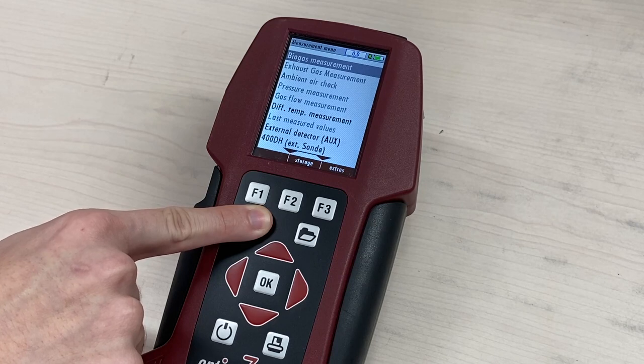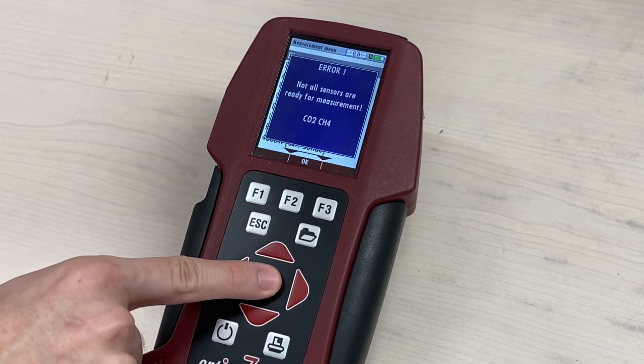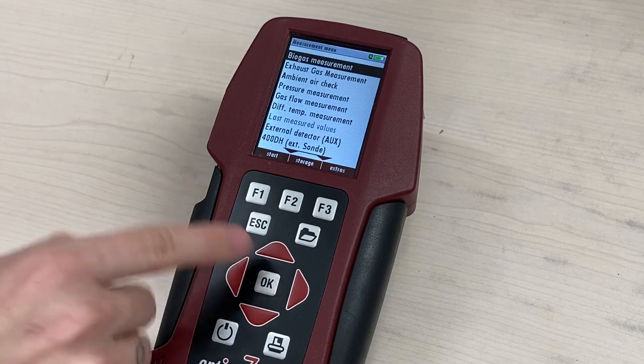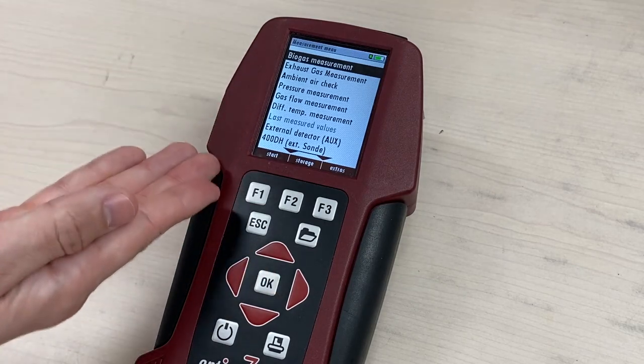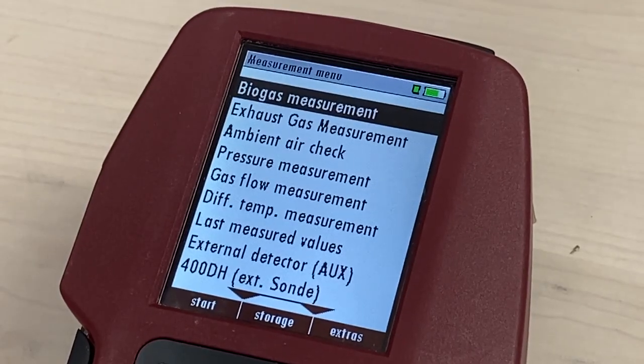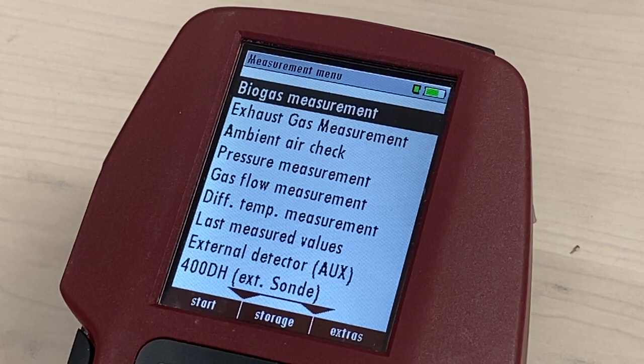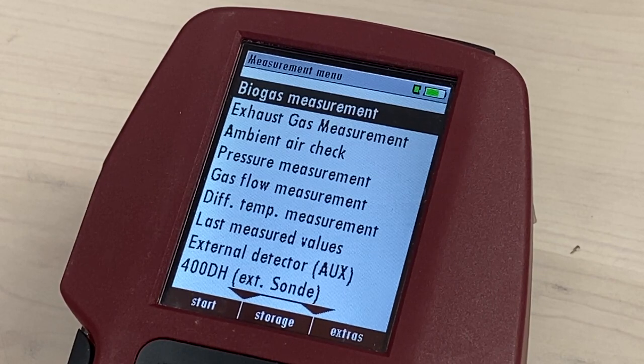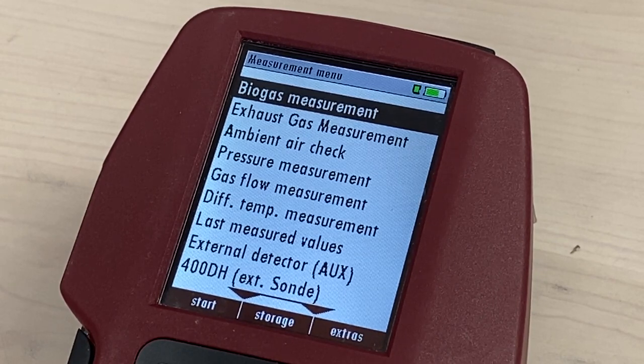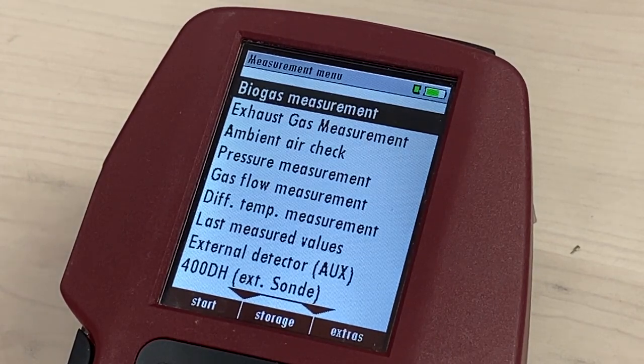If you skipped the auto-zeroing process, press OK to acknowledge the instrument is not zeroed. The default measurement menu will display. Biogas measurement will be highlighted.